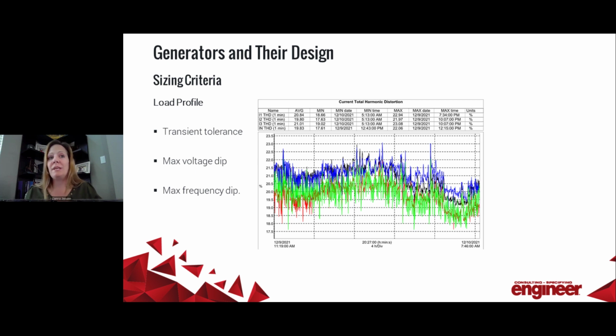And for sensitive equipment, such as medical imaging equipment, there are data sheets that say the equipment can only tolerate a plus or minus 2% frequency variation. So with sensitive loads such as these, it may be more prudent to apply a power conditioner or a UPS upstream to help ride through the start of the generator system and protect the loads, as opposed to increasing the alternator yet again.